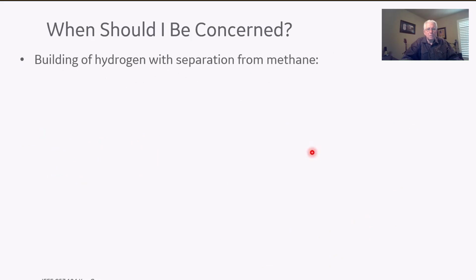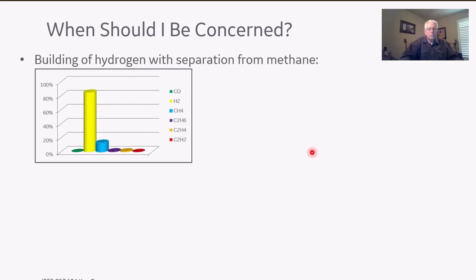So when should I be concerned? Building hydrogen with separation from methane - this came out of C57.104. If you look at this bar chart, you've got quite a bit of hydrogen, a little bit of methane, and the rest of your gases - acetylene, ethylene, ethane - are pretty much flatlined. So hydrogen and methane have a pretty good separation distance between them; that's a pretty good partial discharge signature. And PD at this point, with enough of it generated, can be visible. We've talked about PD before.